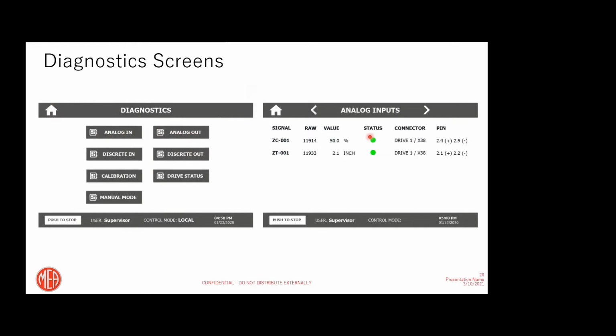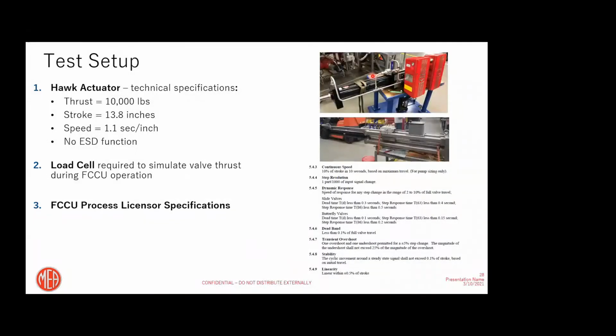So you can easily troubleshoot any of the unit functionality right at the screen and see the status. If there is any loose wire or loose connection, this will turn red and you'll know right away what's happening with the unit. Of course, we didn't end up just talking here about how these units work in general. We actually went ahead and tested this unit.